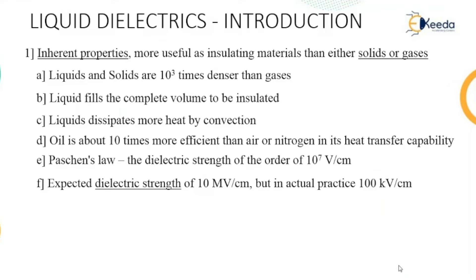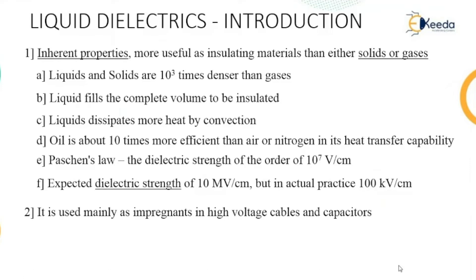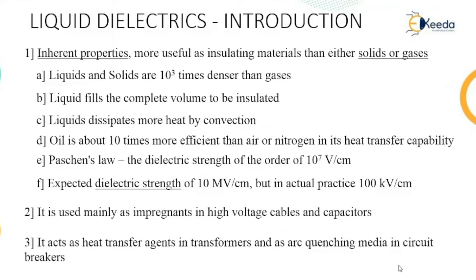Oil is almost 10 times more efficient than air and nitrogen in terms of heat transfer capability. According to Paschen's law, the dielectric strength is of the order of 10^7 volts per centimeter, and the dielectric strength in liquids is expected to be 10 megavolts per centimeter as per Paschen's law, but in practice we get around 100 kilovolts per centimeter. This liquid can be used in cables and capacitors as an impregnant, as a heat transfer element for transformers, and to quench the arc as a medium in circuit breakers.